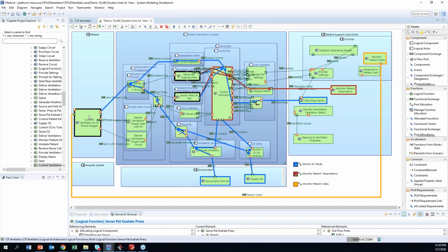Yep. In many cases, you would use tools that can model different pieces of hardware, such as compressors. You may have a 1D model that represents the circuit that connects the patient to the ventilator. And then there's even the possibility of developing a model of the patient itself. Differential equations are pretty common for doing that. I ran into one white paper recently that had that.